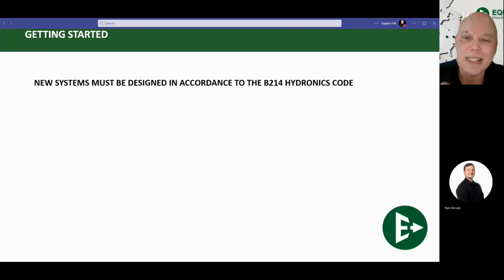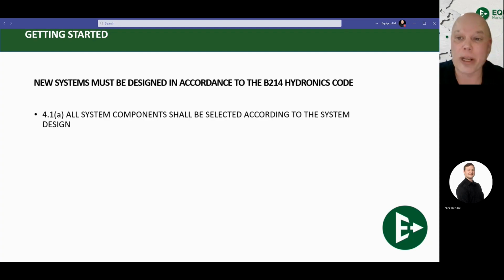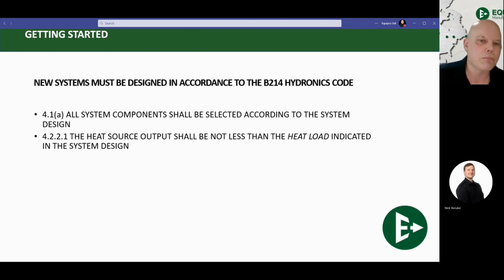So here are some things to note. The new systems must be designed in accordance with the CSA B214 Hydronics Code. And here are some of the key takeaways that I like with regards to the Hydronics Code that you can use to make sure that you sell your projects properly. 4.1a: All system components shall be selected according to the system design. That means that someone owns the design for this system. If the contractor does it themselves, that's fine. If they get someone with a BCIN to do it, again, completely fine, and that's usually the better way because that carries some liability insurance, or maybe they're going to get a P.Eng. to do the design. Doesn't matter who, but someone legally owns the design of that system and says, yes, this will work. Keep that one in mind.